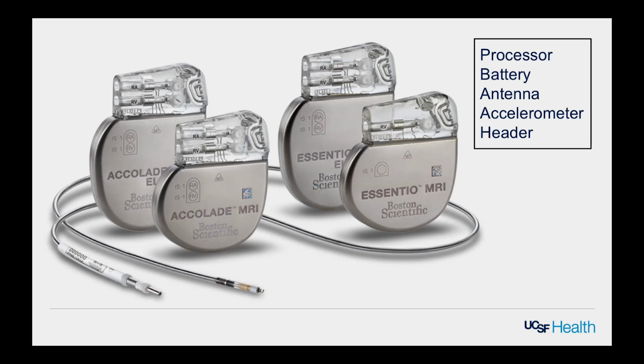So a pacing system is comprised of a generator, and these are 4 different examples of pacemaker generators, and a pacemaker lead. So the lead is actually what goes in through the vein into the heart, and the lead is then connected to the generator. And you can see down here in the bottom left, there's a pin at the end of the lead, and that pin is placed in this header, and there's a screw within here that we tighten down, and that attaches the lead to the actual pacemaker generator.